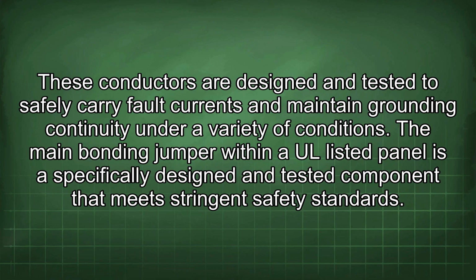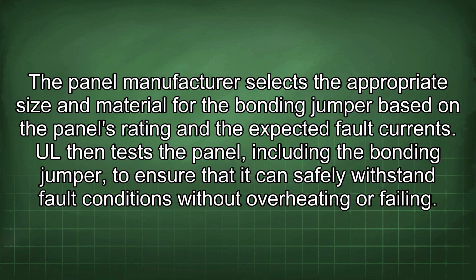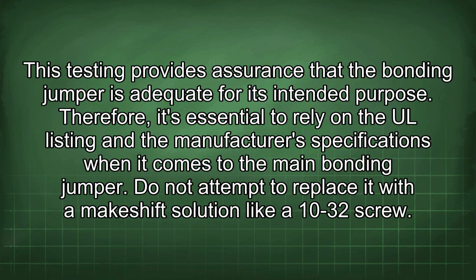The main bonding jumper within a UL-listed panel is a specifically designed and tested component that meets stringent safety standards. The panel manufacturer selects the appropriate size and material for the bonding jumper based on the panel's rating and the expected fault currents. UL then tests the panel, including the bonding jumper, to ensure that it can safely withstand fault conditions without overheating or failing. This testing provides assurance that the bonding jumper is adequate for its intended purpose.